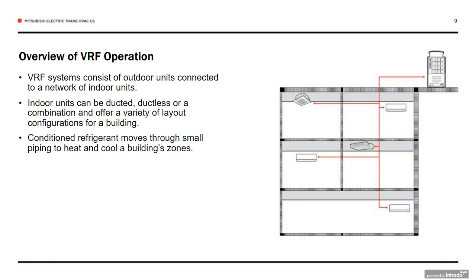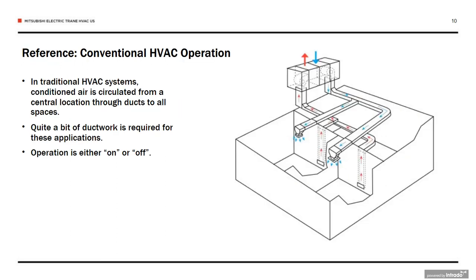Now, before we jump into the benefits, let's review how this technology works. Here you can see a diagram of the outdoor unit connected to the indoor units via the red piping. The indoor units are in the zones and can be ducted or ductless. The entire VRF system is connected and controlled via standard controls that come with the system to communicate with all the components, whether it needs to deliver heating or cooling.